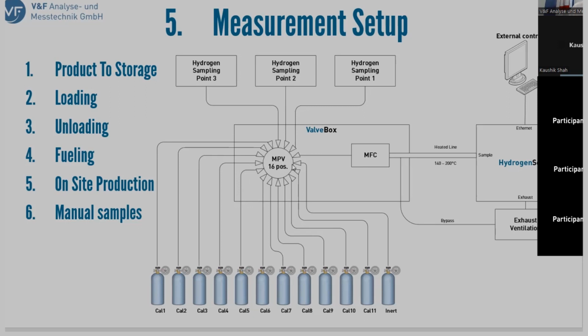All of these positions are automatically controlled by our software. So it's pretty much just a click of a mouse to select one of the positions. Once the valve has switched, the gas will be provided to the mass flow controller, where we have a heated line which goes towards the mass spectrometers, and an overflow line which will bypass all the gas which is not used by the spectrometers.